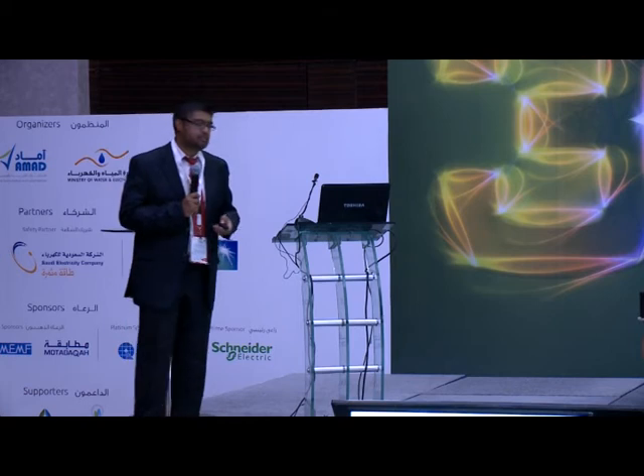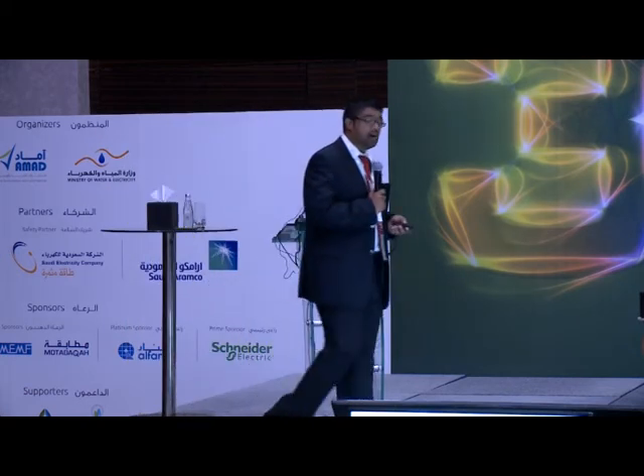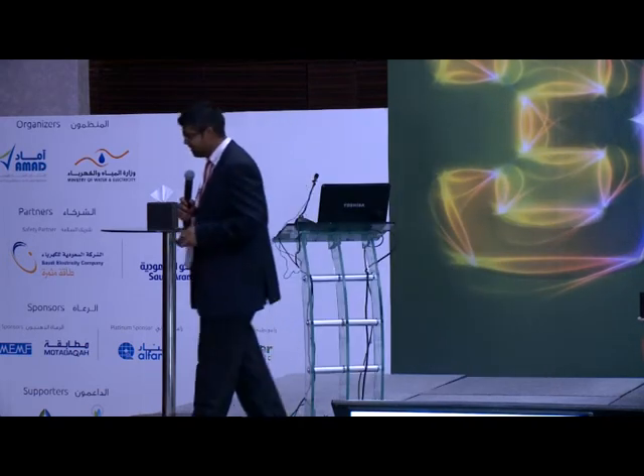So we refer to live, dead, live type of testing, and E is for earthing where applicable. Obviously on your Delta systems, which have no reference to earth, earthing would be pointless and create a greater hazard in that case. Okay, habit number 6, we refer to identifying a greater hazard.